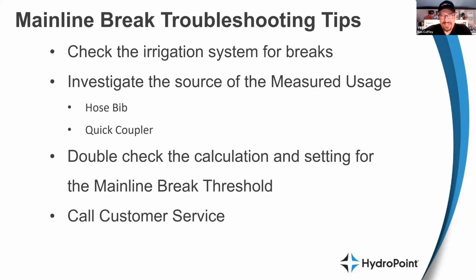I have a question. I think this is from South Africa. They are asking for a simple definition of the mainline break alert. And the most simple definition of the mainline break alert, just to recap, is that we set a system-wide threshold. We call that the mainline break threshold. And if our measured usage ever passes the system cap, the top of our expected usage, then it will prompt a mainline break alert. Once your measured usage passes your mainline break threshold, then it will give you that mainline break alert, and it can be any one of these issues that we're talking about.